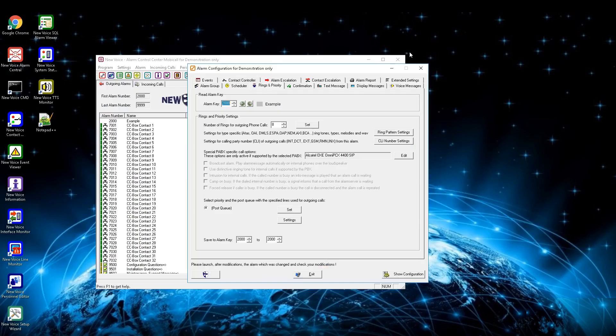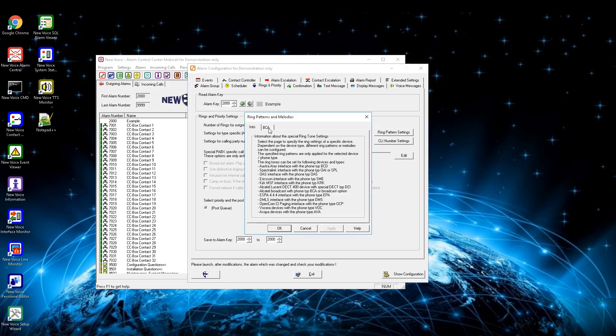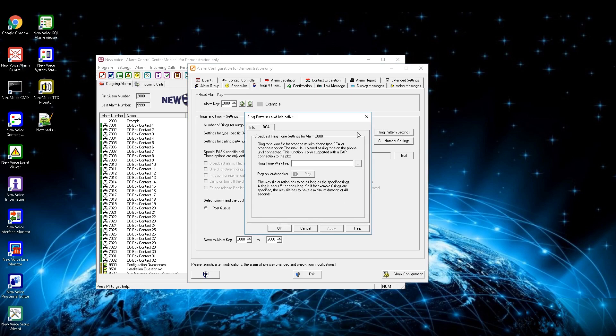Within the rings and priority settings window you can define different options for the call in this alarm. First is the option number of rings for outgoing phone calls — the default value is 8 calls, where 1 call equals 5 seconds, so by default the phone rings for 40 seconds. You can turn this value up or down and press set when changes are made. Next is the ring pattern settings, where you can define different ringtones for different devices — this needs special settings like DECT or Alcatel special configurations.